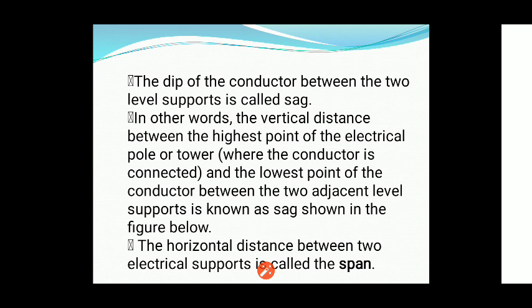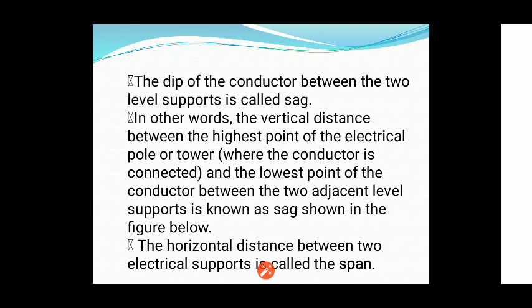The dip of the conductor between two level supports is called sag. In other words, the vertical distance between the highest point of the electrical poles and the lowest point of the conductor — this difference is known as sag. The horizontal distance between the two electrical supports is called the span.